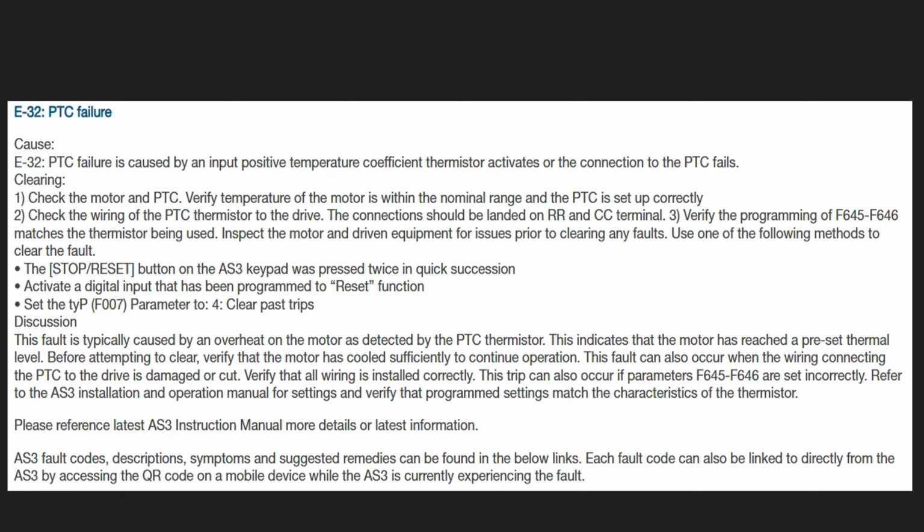If it is still the same, there could be an issue in the motor. If it is occurring frequently, there could be an issue in the motor. You need to repair your motor or check your motor. And if it is occurring continuously when you have proper settings and values, and wiring is also proper, there could be an issue in the terminal of the VFD. That also could be damaged, like the control card or the VFD could be damaged.